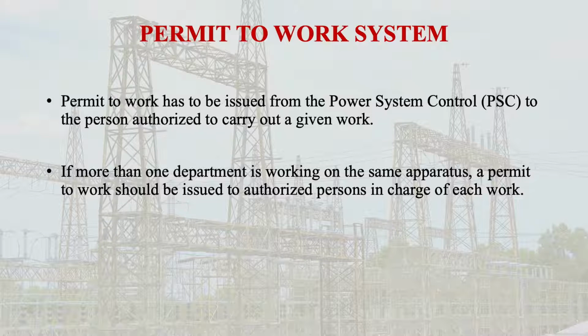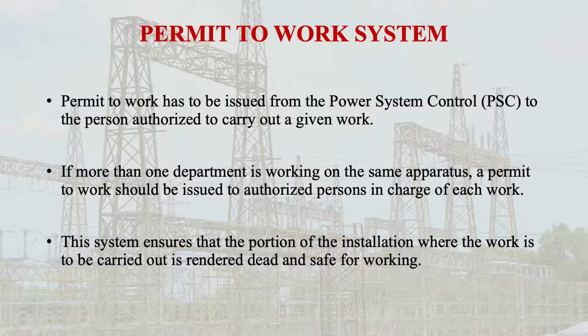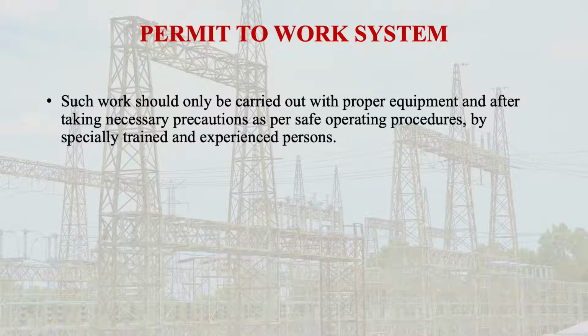All work has to be carried out under the personal supervision of an authorized person. If more than one department is working on the same apparatus, a permit to work should be issued to the authorized person in charge of each work. This system ensures that the portion of the installation where the work is to be carried out is rendered dead and safe for working. Such work should only be carried out with proper equipment provided for the purpose and after taking necessary precautions as per the rules or safe operating procedures, by specially trained and experienced persons who are aware of the danger that exists when working on or near live mains or apparatus.